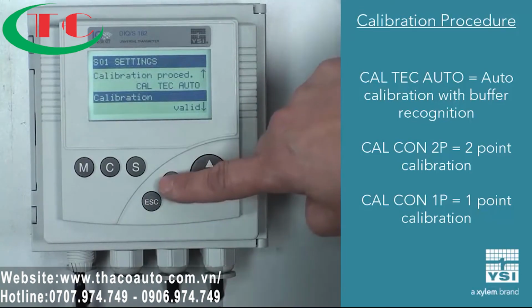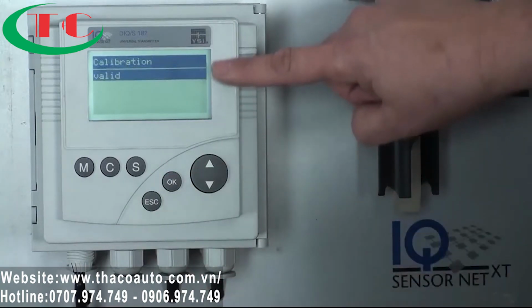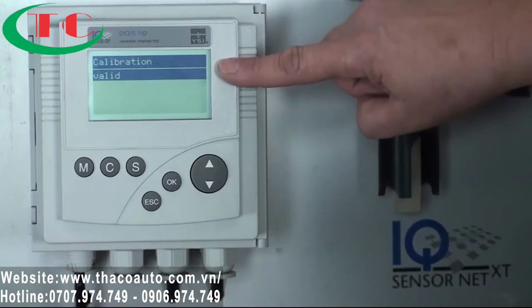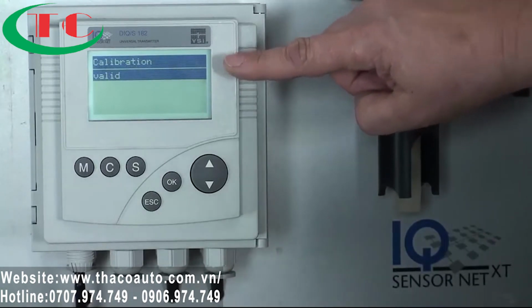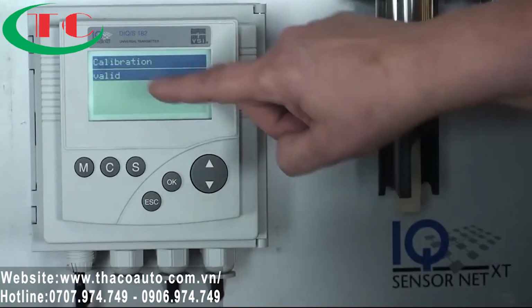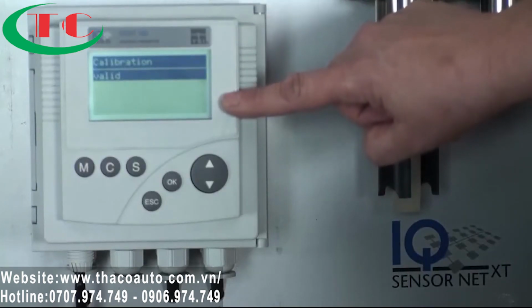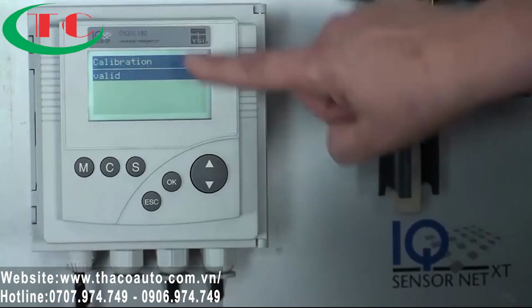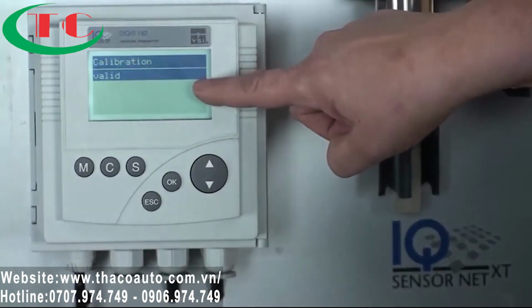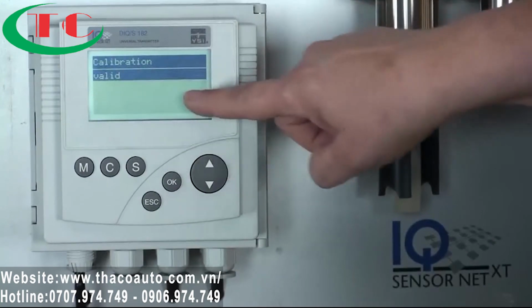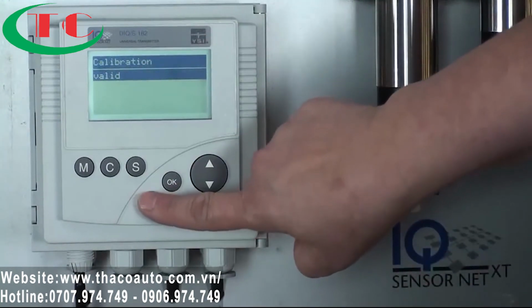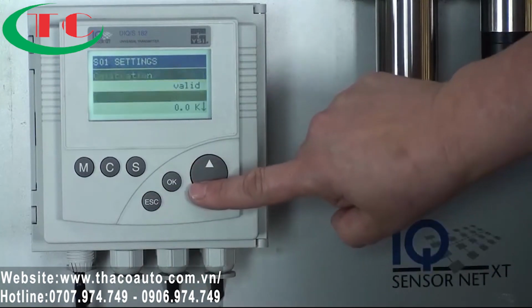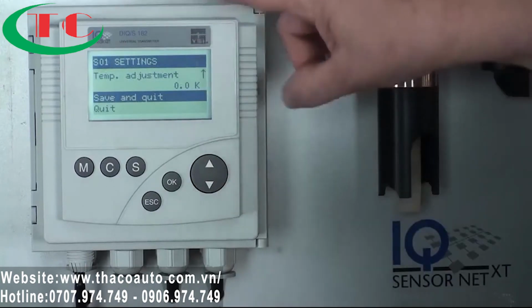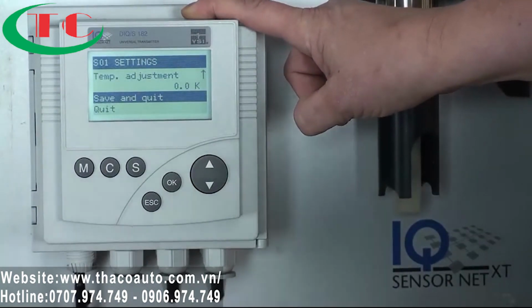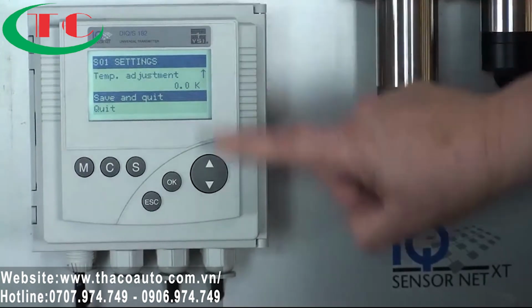Our calibration is valid. Now, if I had just done another calibration and it was invalid, and I came up with a bunch of lines for the sensor, for the calibration, it was blocked for measuring, I could come back into this screen and I would have a second choice here. It would say invalid, and then I would have last valid calibration. I could choose that, and it would put the sensor back online until I could get a new electrode. Temperature adjustment, save and quit. If you've made any changes, make sure that you save and quit. Otherwise, you've just kind of gone through it for no reason.